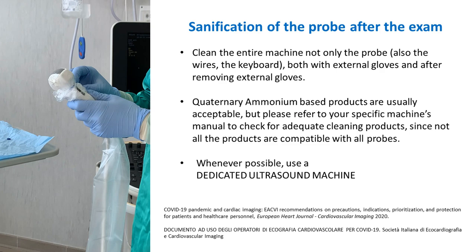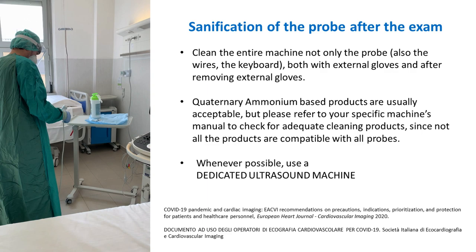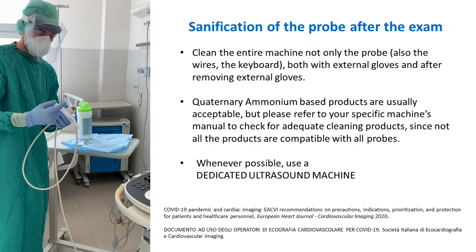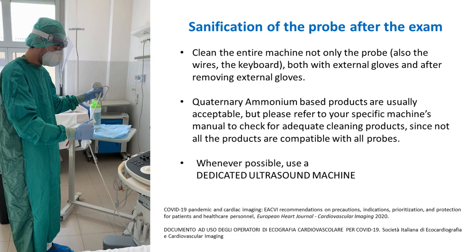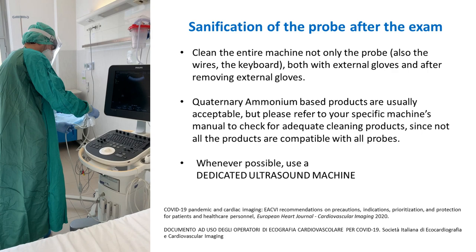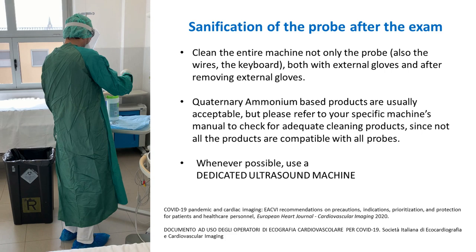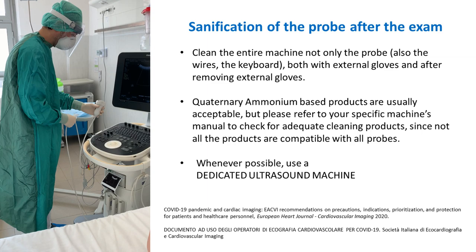When the exam is finished, both the probe and the machine should be properly cleaned. The cover should be removed and discarded. The probe should be properly sanitized — we can use specific wipes or other products to clean the probe, the wires, and also the keyboard and other surfaces. We recommend reading the user manual of your echo machine to select the appropriate product. It is advisable to do a first cleaning round with the patient-specific gloves, and then after correctly removing these gloves, clean the surfaces again. If possible, a dedicated machine would simplify these procedures and reduce the risk of spreading infection.